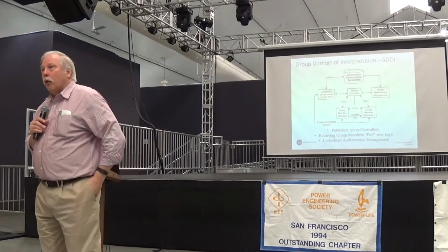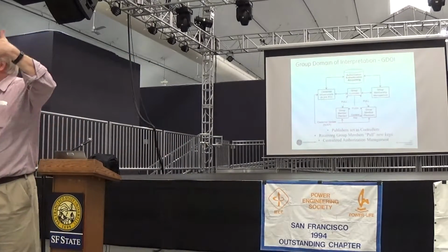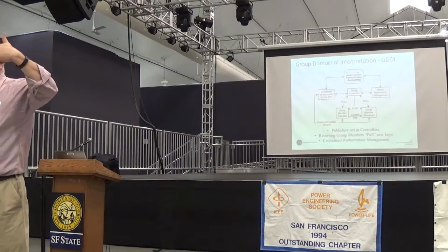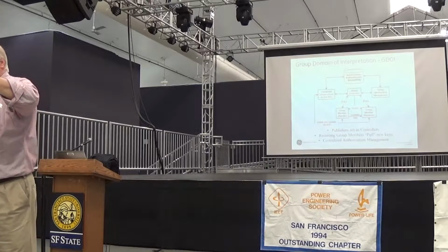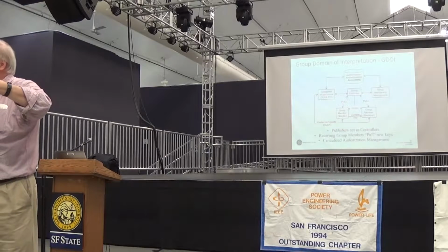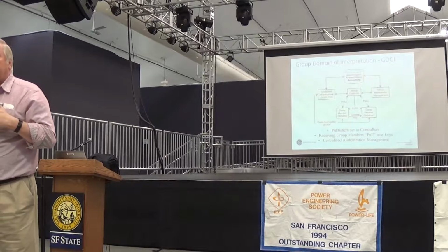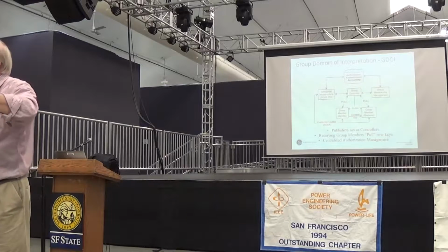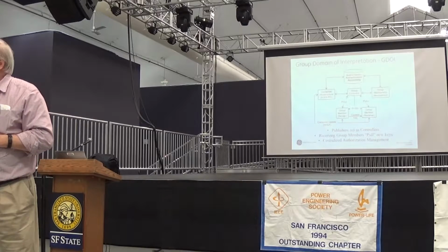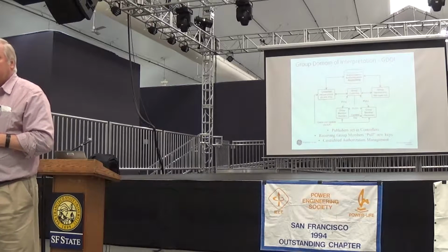In the utility world, dependability is key. If there's a fault on the system, I have to be able to trip to clear that fault. If a remedial action scheme requires a control message, I have to be able to transmit and receive that remedial action message. That trumps security.